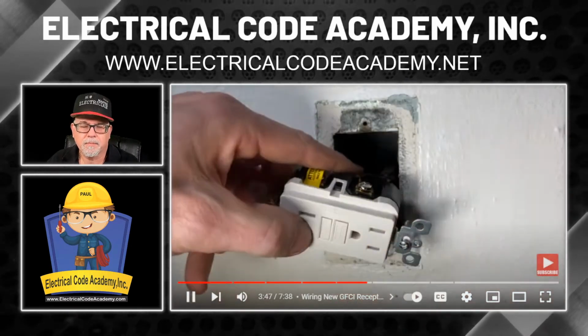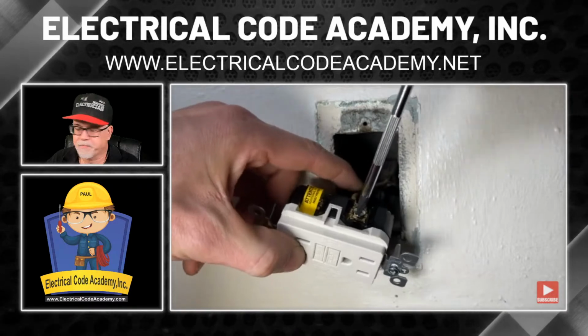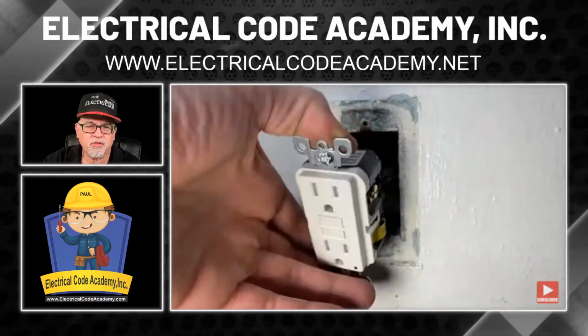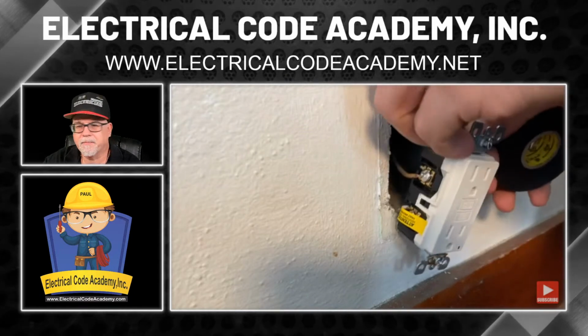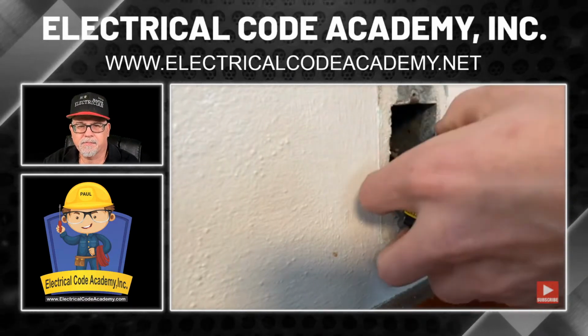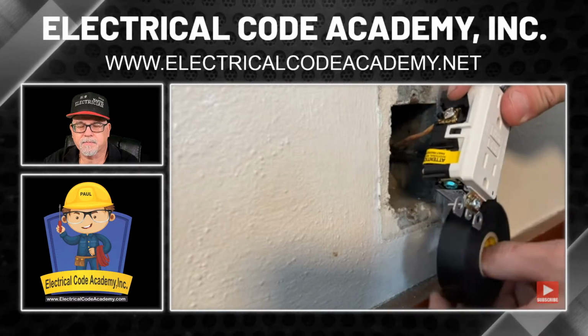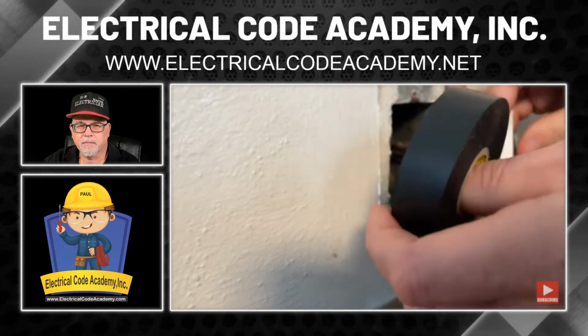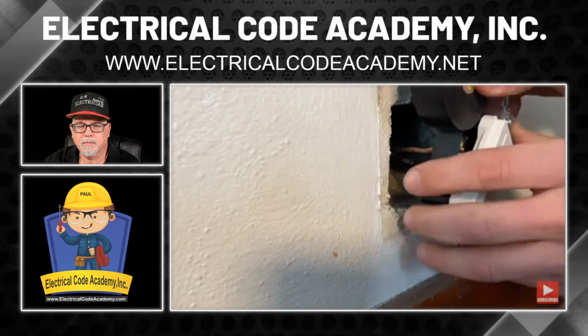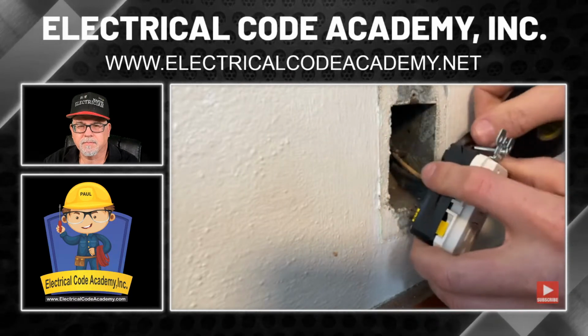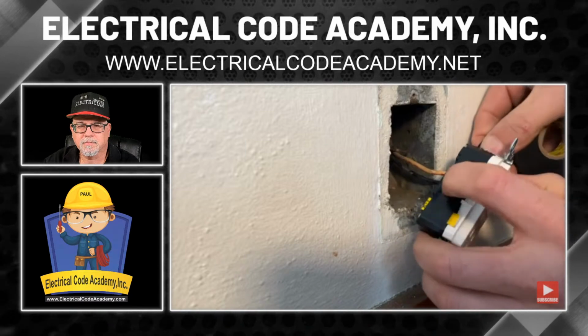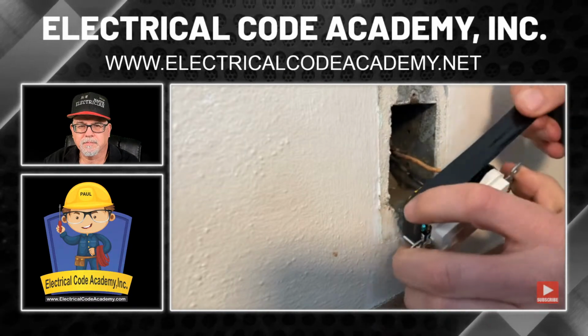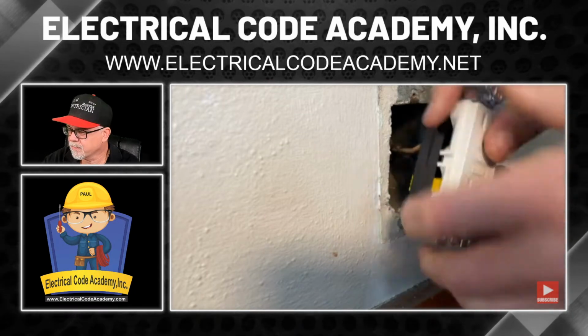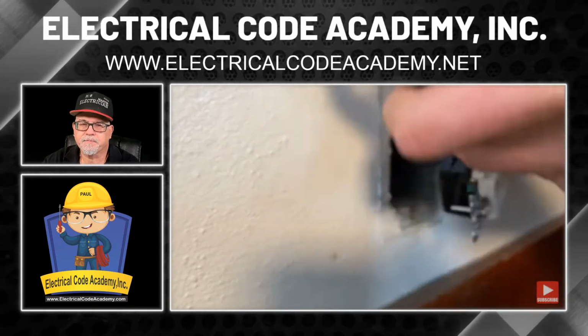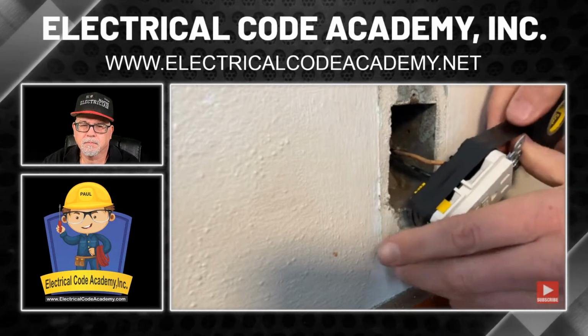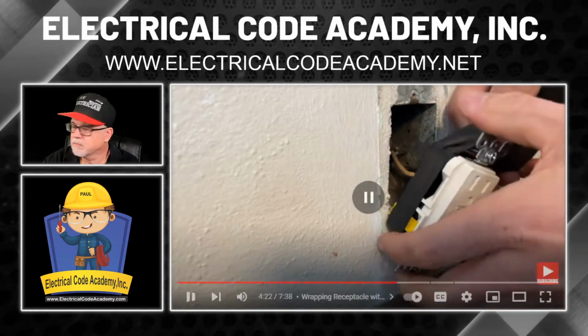Underneath the plate, making sure no exposed copper is going past the housing. Notice how hardly any room to work there is now with this. Before placing a GFCI outlet in the metal box, because it's so tight, I'm actually going to wrap with 3M Super 33 Plus electrical tape. Best tape on the market. And you can see the link in the description, which will show you exactly what I use. I'll do 2 wraps, stretching the electrical tape as I go on the outside, and that will help bond the tape and also contour to the receptacle housing.